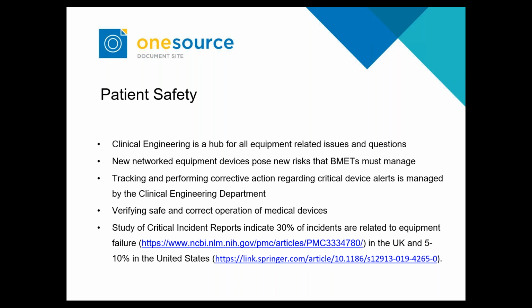And also, tracking and performing corrective action regarding critical device alerts is managed by the clinical engineering department. So if there is a device with some manufacturer defect, it's the clinical engineer's responsibility to take that out of service and make the corrective action if necessary. Without the clinical engineers doing this, it can lead to preventable patient catastrophes or patient harm. So that's another way that BMETs directly assist in patient safety.